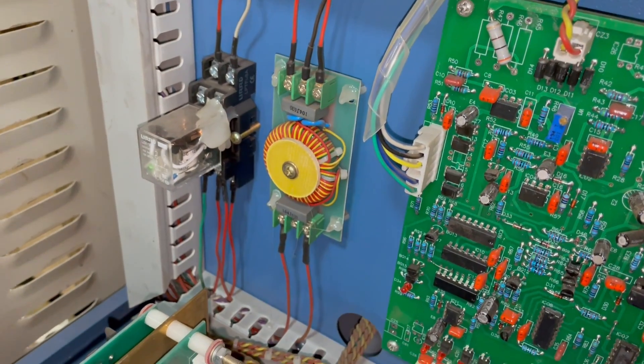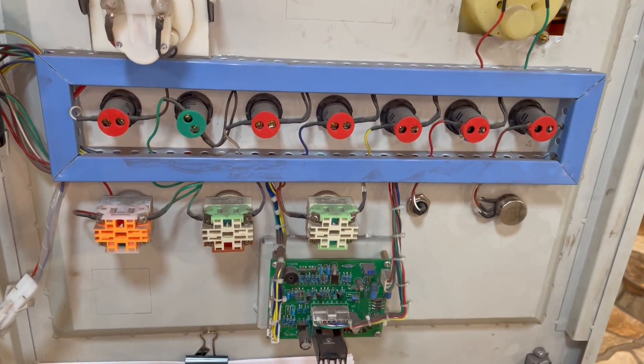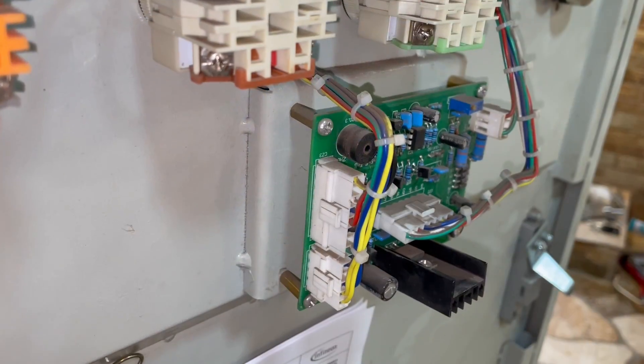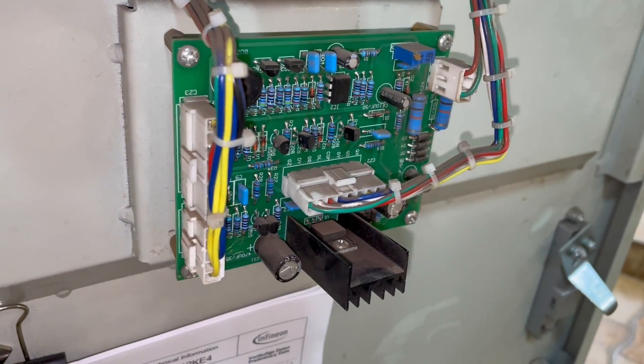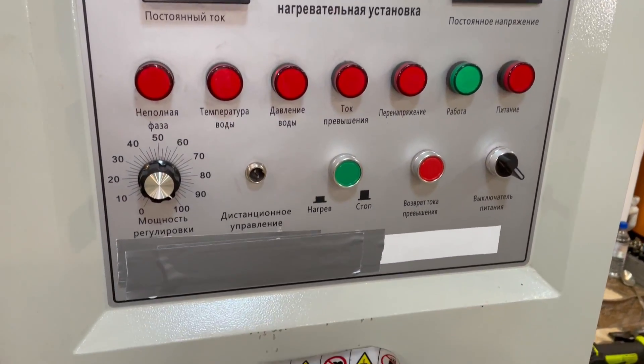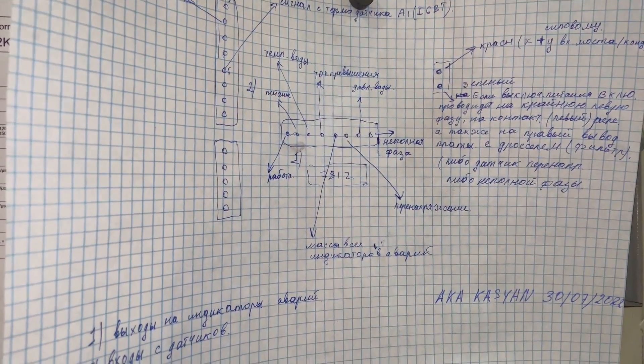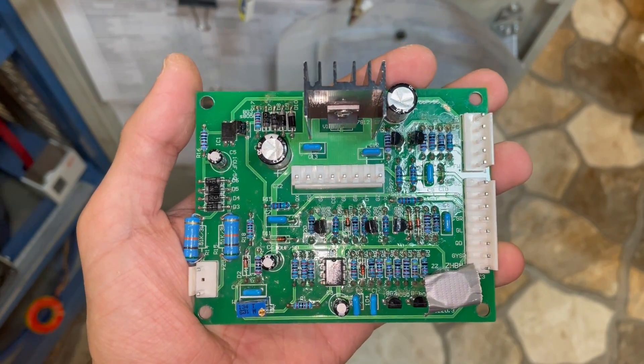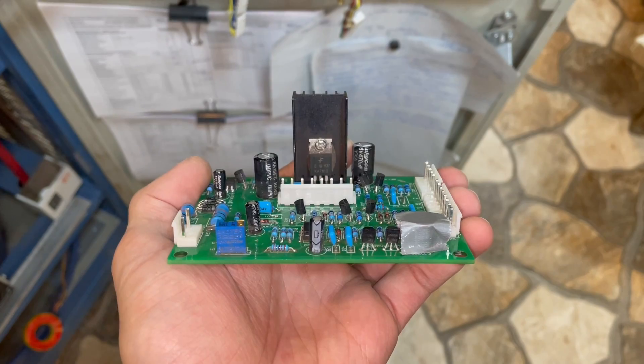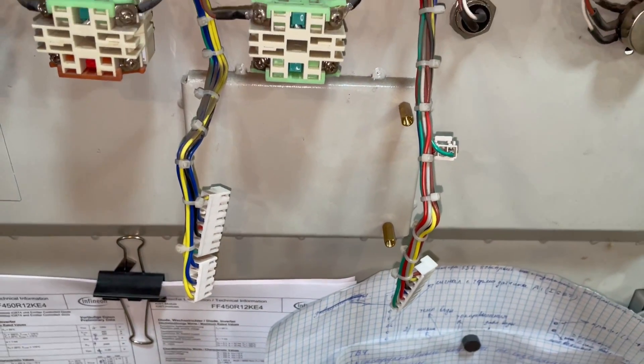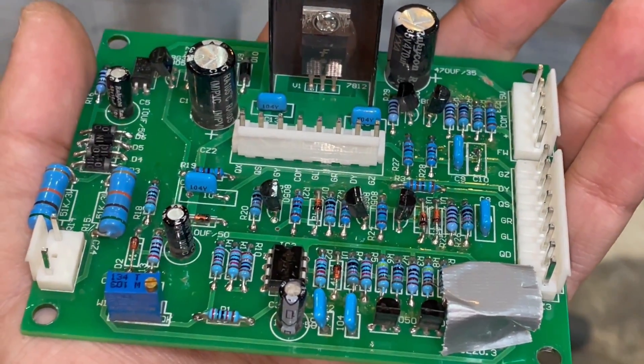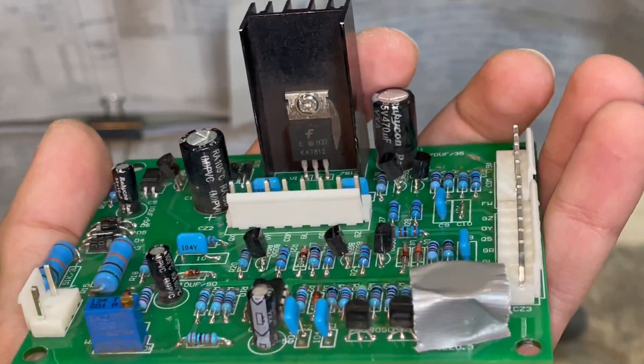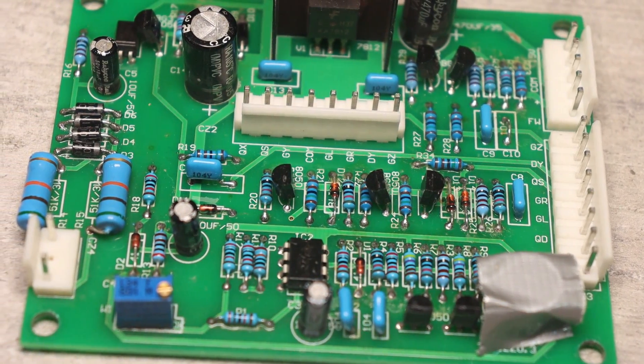And then we have a board which is on the front panel. This board provides monitoring of data from all sensors and also illuminates a certain alarm LED on the front panel. Using the multimeter I made the pinout of this board. It is painfully simple despite the large number of sensors. Four or five thermal sensors, a water pressure sensor, phase control, current and over-voltage control.